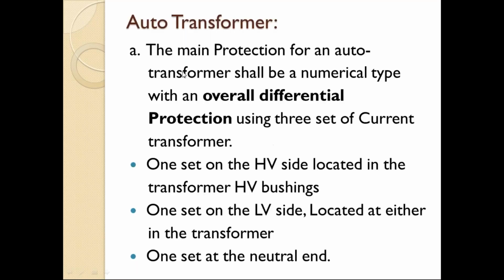What is this auto transformer and what will it be connecting? This is the HV side, as you see from the rating, 400/132 kV. Below this, the transformer is the 132 kV side. This area is the transformer overall protection. Similarly, the HV side, the LV side, plus the neutral side: these three give the transformer overall protection.